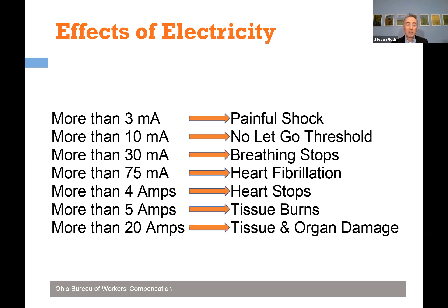The reason I focus on 5 amps and below is that circuit breakers, which protect our systems from overcurrent, are typically rated at 15 amps minimum in a residence, and 20 amps in a commercial or industrial building. Yet all of these harmful effects, even tissue and organ damage, happen at 20 amps or below. So these overcurrent protection devices are there to protect the equipment and the building structure - they are not there to protect you. So we have to talk about what's in the electrical system that protects us from injury.